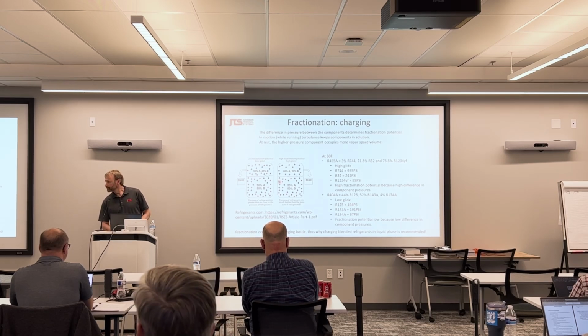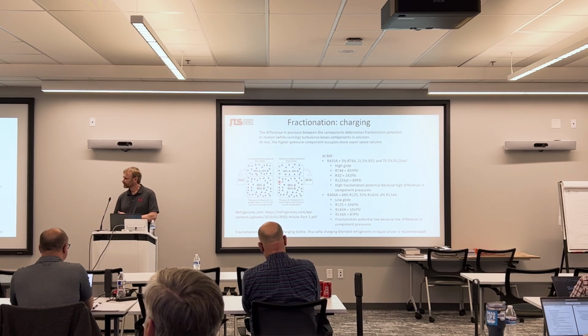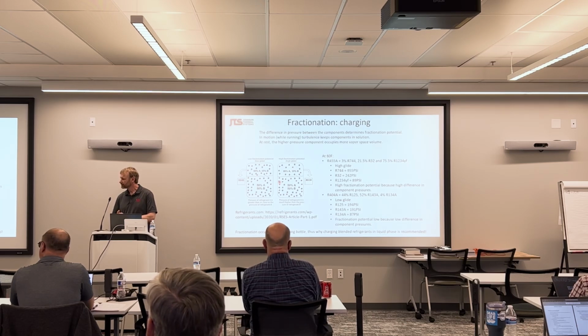Question on that for a moment. Yes, sir. Let's say I'm out in the field and I have to add additional charge, and I don't have a transfer pump, so it would be difficult for me to charge with a liquid. If I have to add, say, 5, 10 pounds to a 100-pound system, I'm probably gonna charge through the suction line as a vapor. How critical is that?